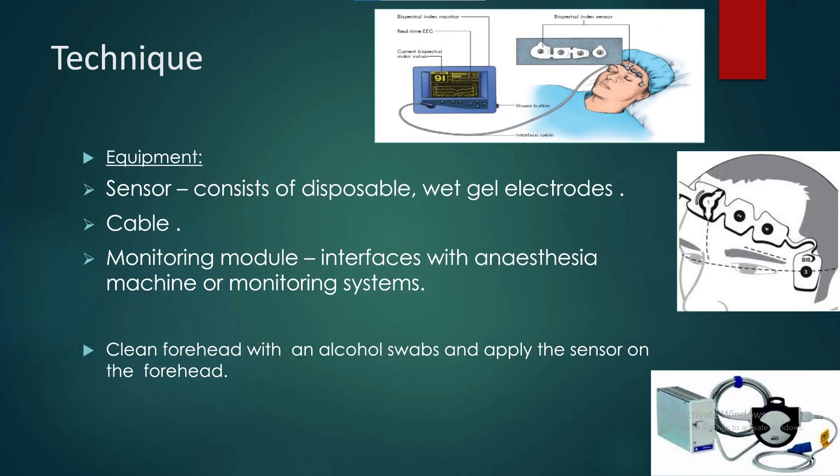Technique and Equipment: the sensor consists of disposable wet gel electrodes and a cable. The monitoring module interfaces with the anesthesia machine or monitoring systems. Clean the forehead with an alcohol swab and apply the sensor on the forehead.